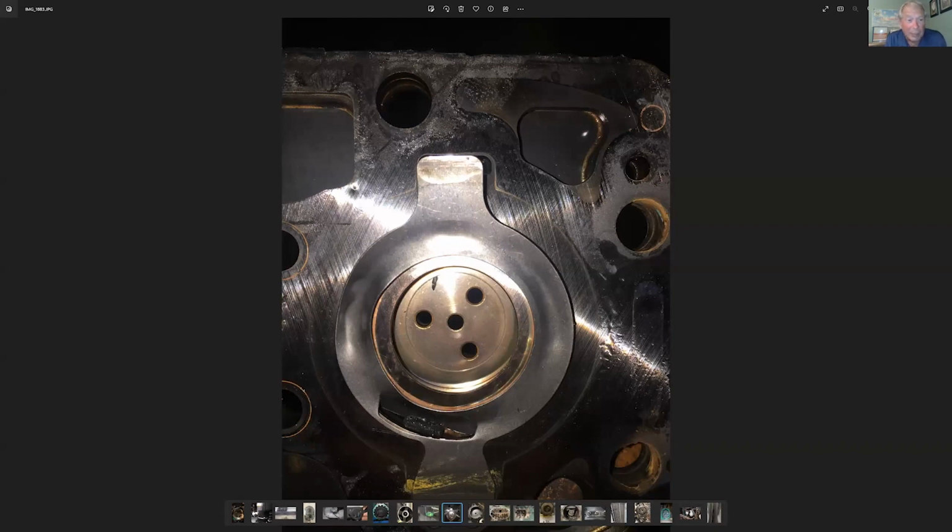But anytime a liquid has a chance to build up in the crankcase of that compressor during the off cycle, and that's the key, it's off cycle, and then boom, all of a sudden the compressor's doing the Elvis shake, rattle, and roll. If you're ever there, especially with those larger semi-hermetic applications, whether they're Carlisle, Copeland, whichever it be, them puppies will move around like there's no tomorrow. They eventually will slow down and get rid of that, and you pray that no immediate damage happens. But the more often it does it, the more likely the damage.